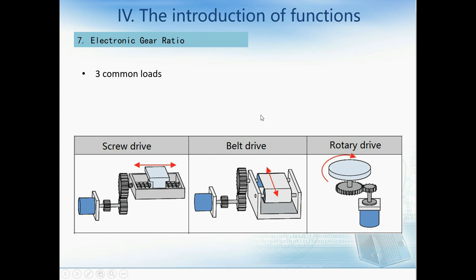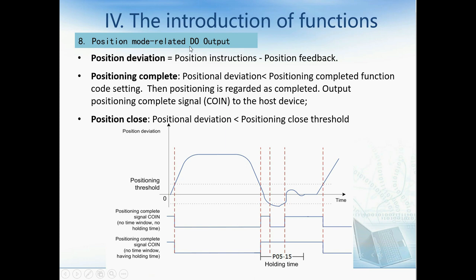Now we talk about position mode digital output. First, the position output signal is the position deviation, which equals position instruction minus position feedback. Second, the digital output signal is position complete — when the position deviation is less than the positioning completed function code setting value, it will output a positioning completed signal to the host device. The third is position proximity closed — when the position deviation is less than the positioning closed threshold, it will output a position closed signal.